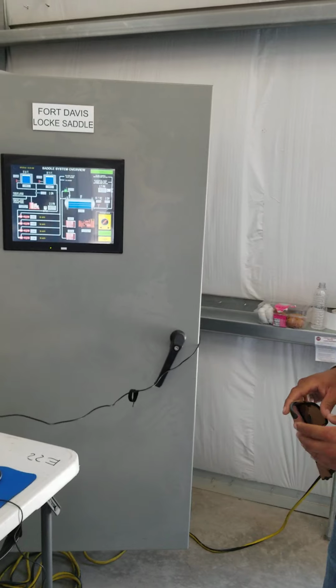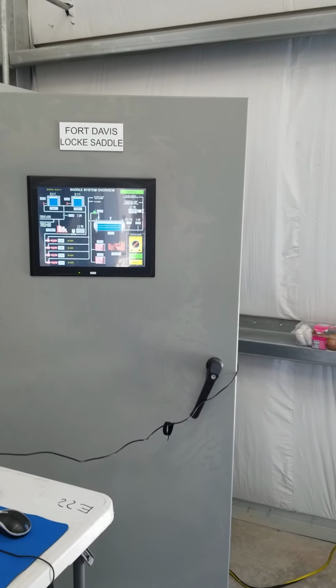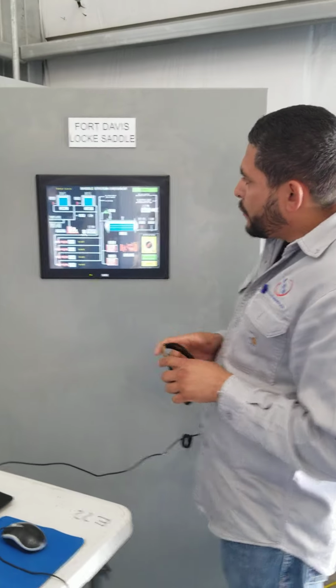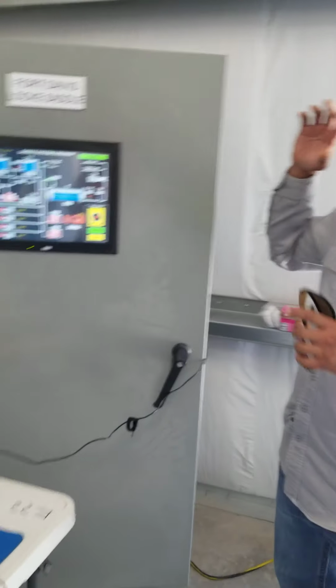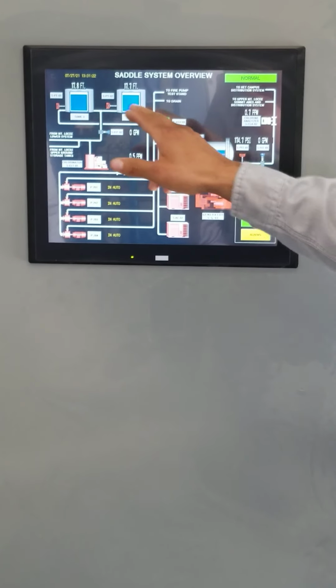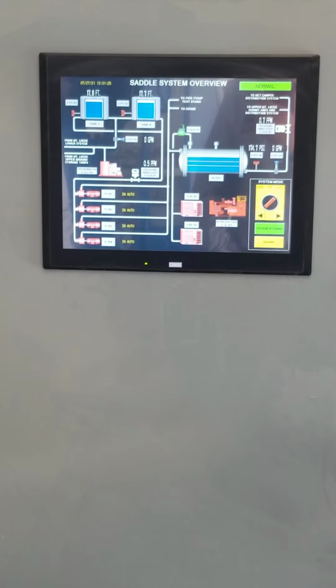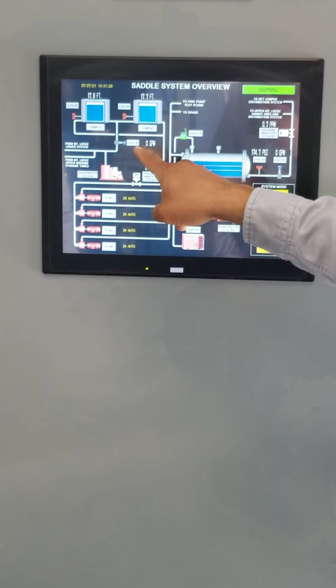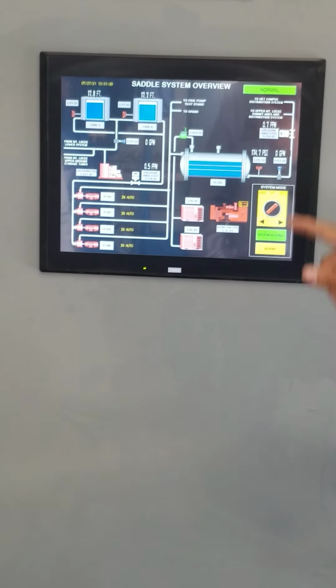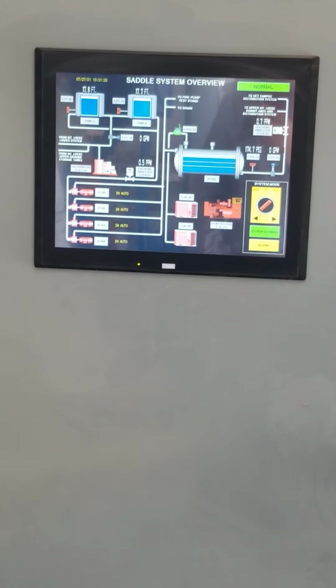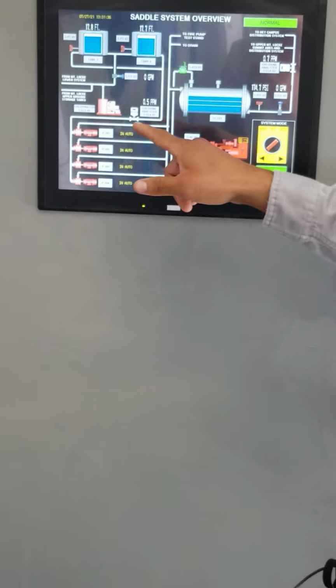So this is a control panel that will control the process of this hydro-pneumatic system. On this first screen we have a system overview. Pretty much gives you the whole process in one screen here. We have the 2 tank levels, which is tank 3 and 4. We have 2 flow meters here, a discharge flow meter and a chlorine feed flow meter. We have statuses for the chlorinator also here. Red means off, green means on, yellow means there's a fault condition.